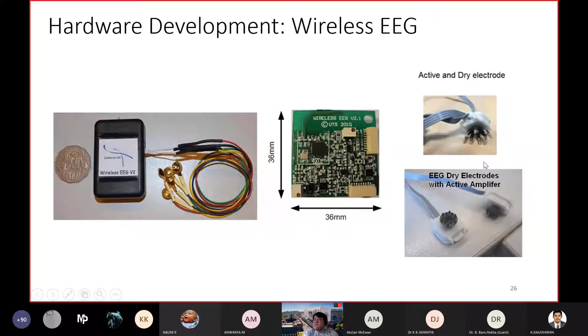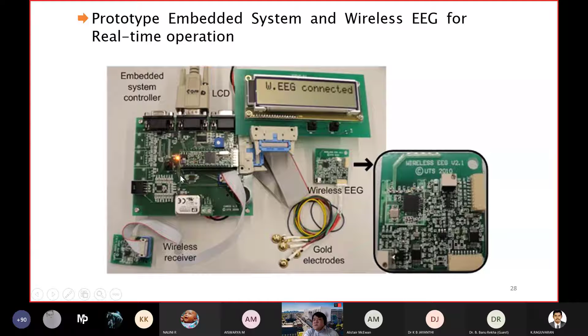So we just need to make sure it is at least comparable to the medical grade of EEG. So this is the whole system. This is the EEG, and this is the embedded system. We use another embedded system to control the computer, basically. And this is testing the system using the EEG that we developed. So we have to make sure the alpha eye-closed is there. You can see here, there's quite a good signal of the alpha eye-closed with the hardware that we developed.